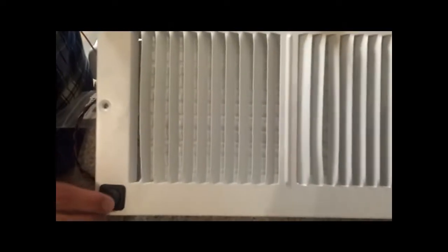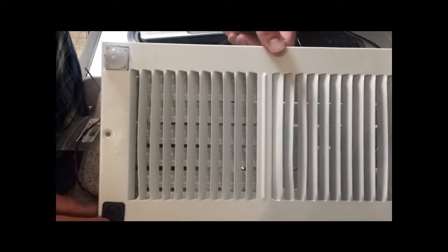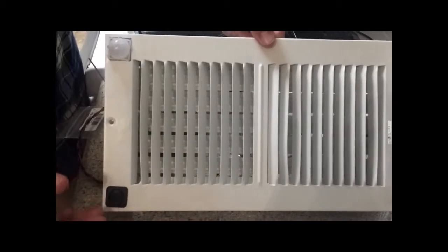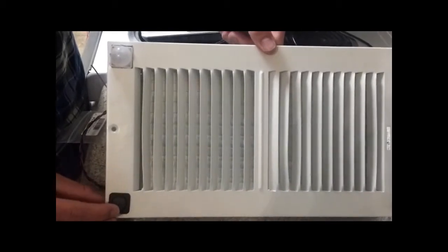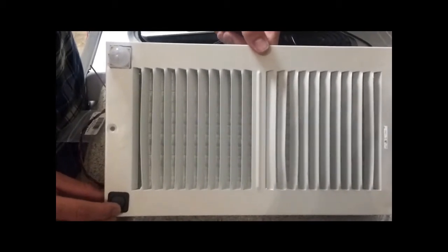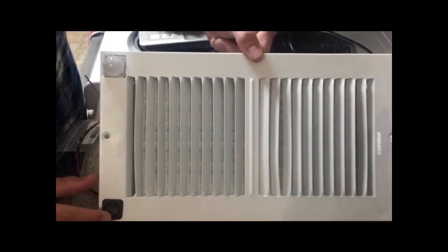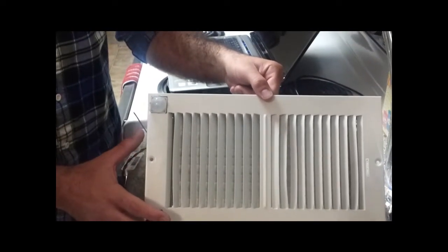So now we're going to demonstrate our override switch. If you come in a little bit closer, you'll see that the vent right now is currently closed. If we switch this switch down, it's going to go into the on position, or the open position. And what this pretty much means is no matter what's going on, your ventilation system is constantly going to stay open, just like your normal vent does in your home right now. If we switch it all the way up, your ventilation system is going to close. So no matter what happens, this vent's always going to be closed. If we go to the middle position now we're currently running on an automatic system, and based off of what the processor is telling you, that's what it's going to dictate whether the vent opens or closes.